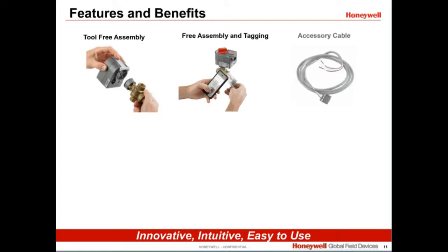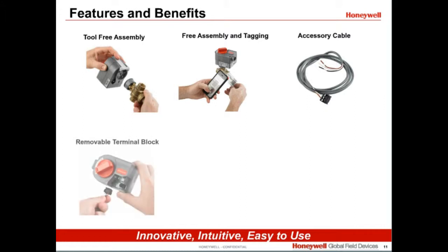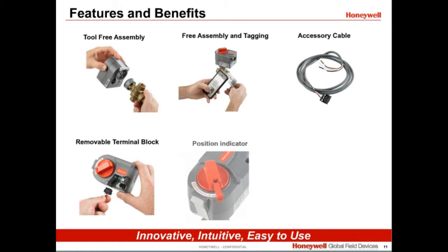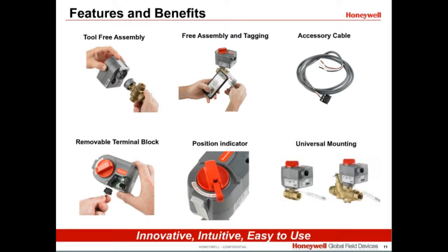The VBN actuator can be ordered with or without a 1-meter cable. To wire a VBN actuator without cables, simply remove the 1 screw from the conduit connection cover. Under the cover is a removable terminal block for easy wiring. The VBN also makes commissioning easy with its manual positioning control knob. The position indicator pulls out from the handle and is visible from below the actuator. The VBN actuator is compatible with both the VBN ball valve and the VRN pressure-independent ball valve.